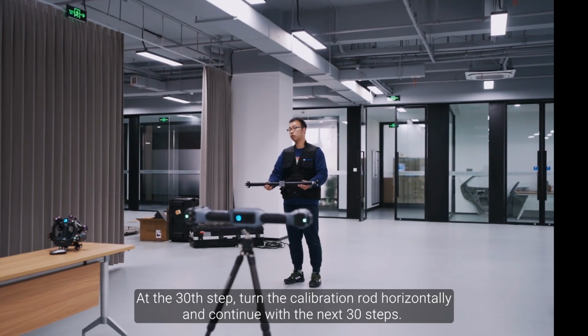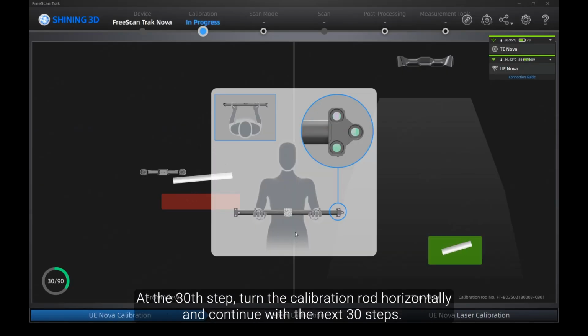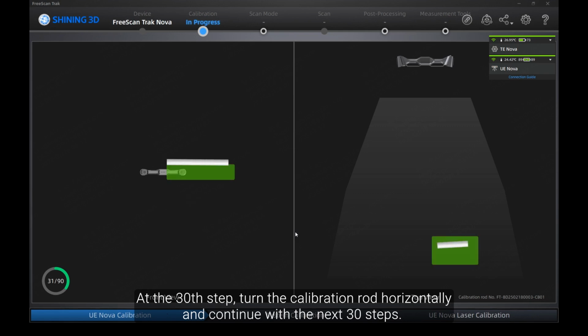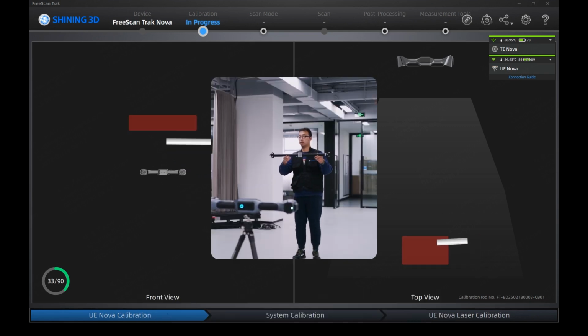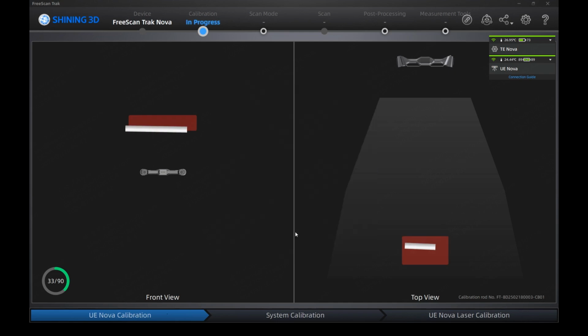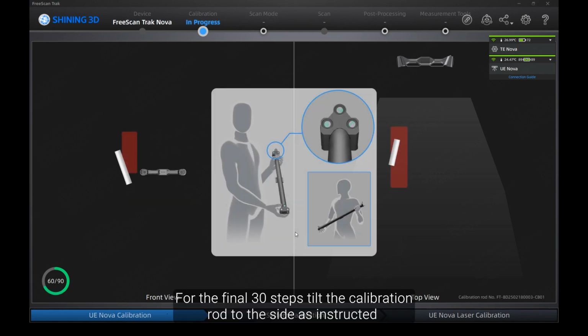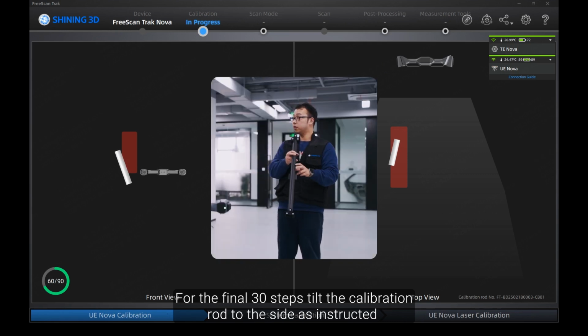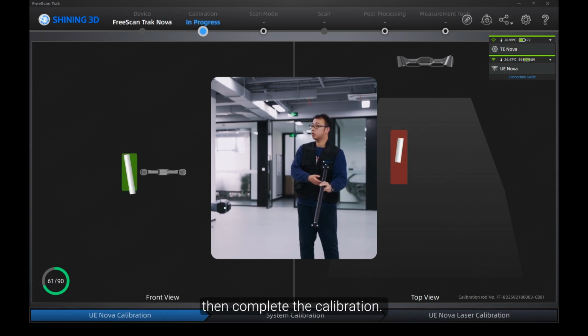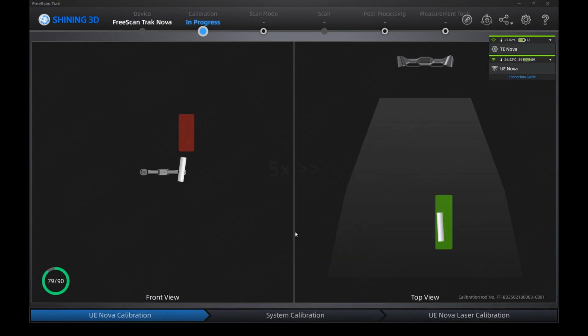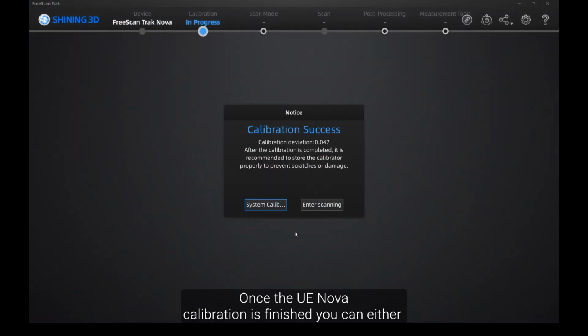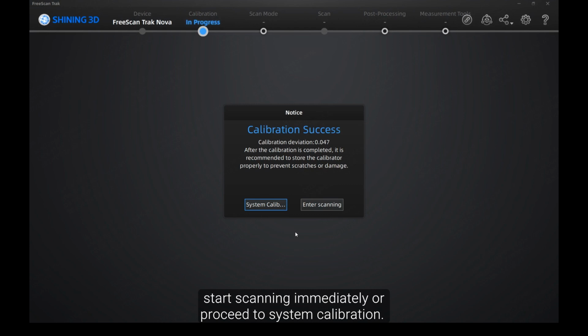At the 30th step, turn the calibration rod horizontally and continue with the next 30 steps. For the final 30 steps, tilt the calibration rod to the side as instructed. Then complete the calibration. Once the UE Nova calibration is finished, you can either start scanning immediately or proceed to system calibration.